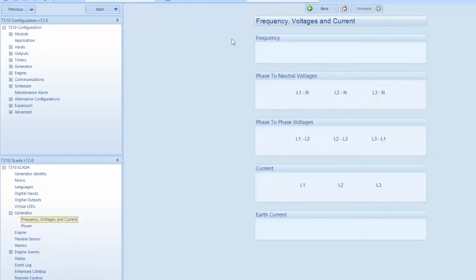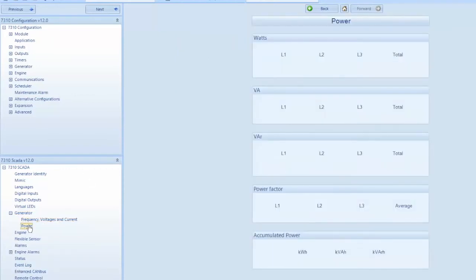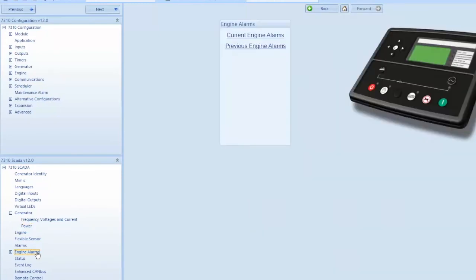It also gives you on a separate screen headed power, watts, VA, VAR, power factor, and accumulated power. From the left hand menu, you can actively monitor your engine parameters as read from the ECU.